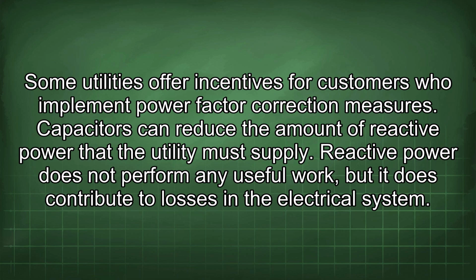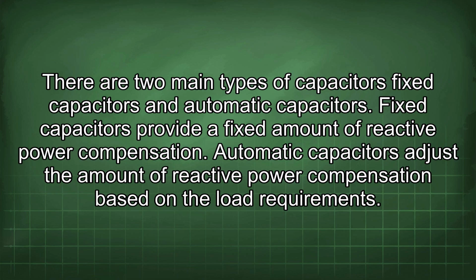Capacitors can reduce the amount of reactive power that the utility must supply. Reactive power does not perform any useful work, but it does contribute to losses in the electrical system. There are two main types of capacitors: fixed capacitors and automatic capacitors. Fixed capacitors provide a fixed amount of reactive power compensation. Automatic capacitors adjust the amount of reactive power compensation based on the load requirement.